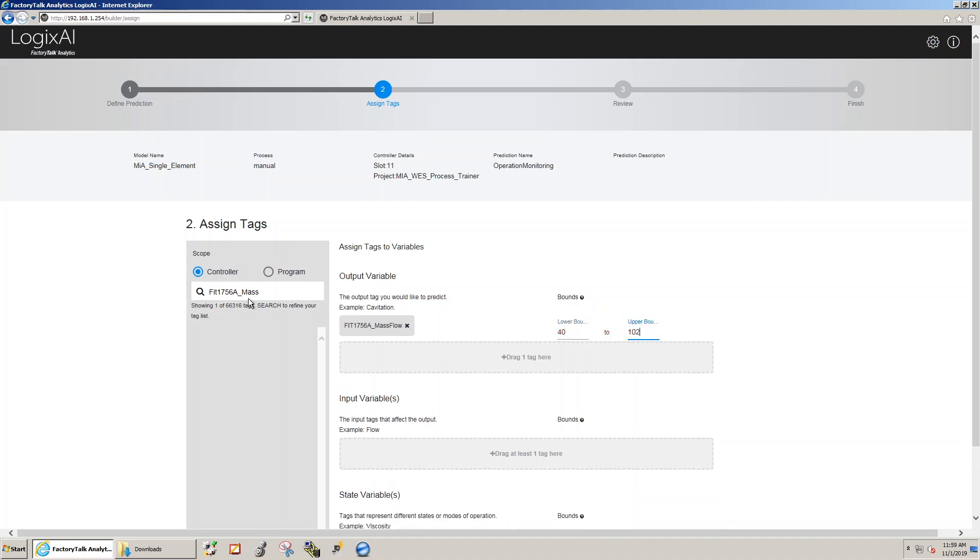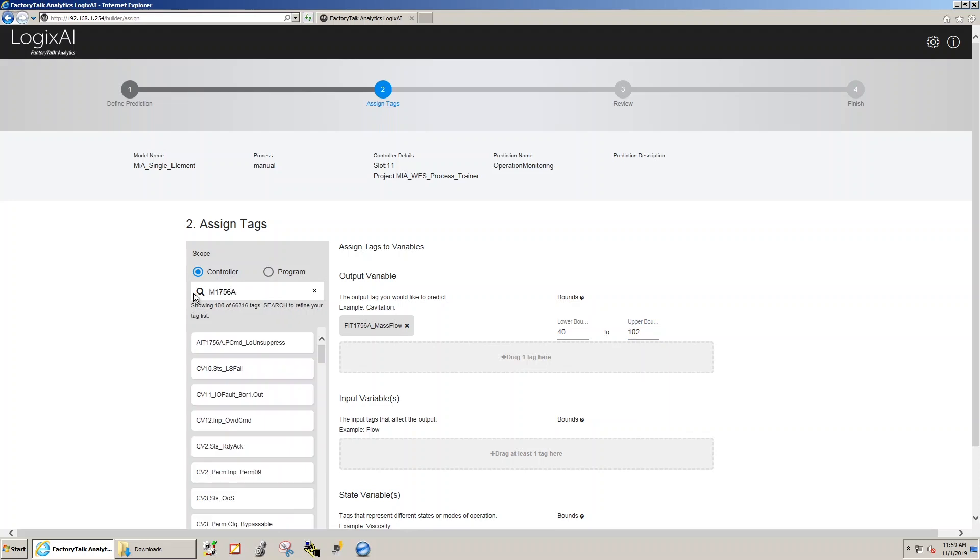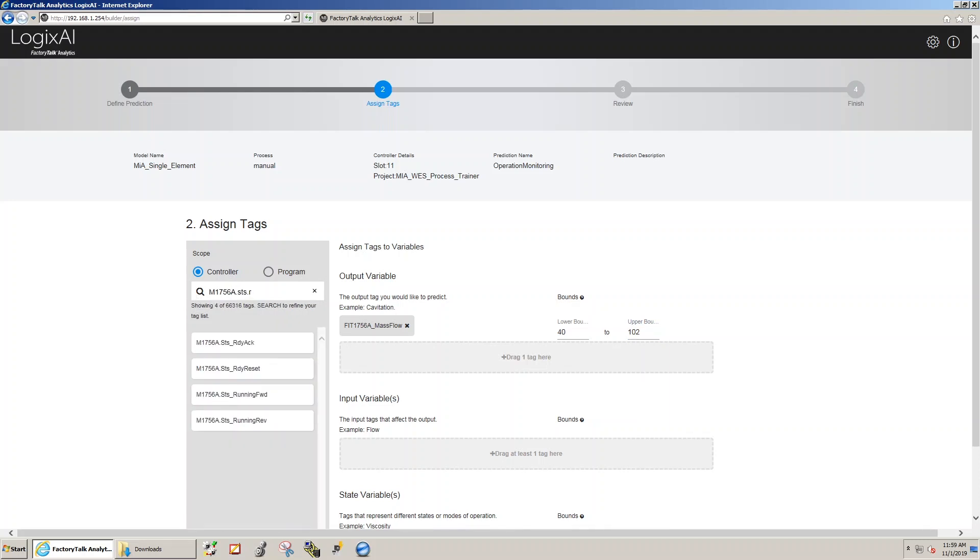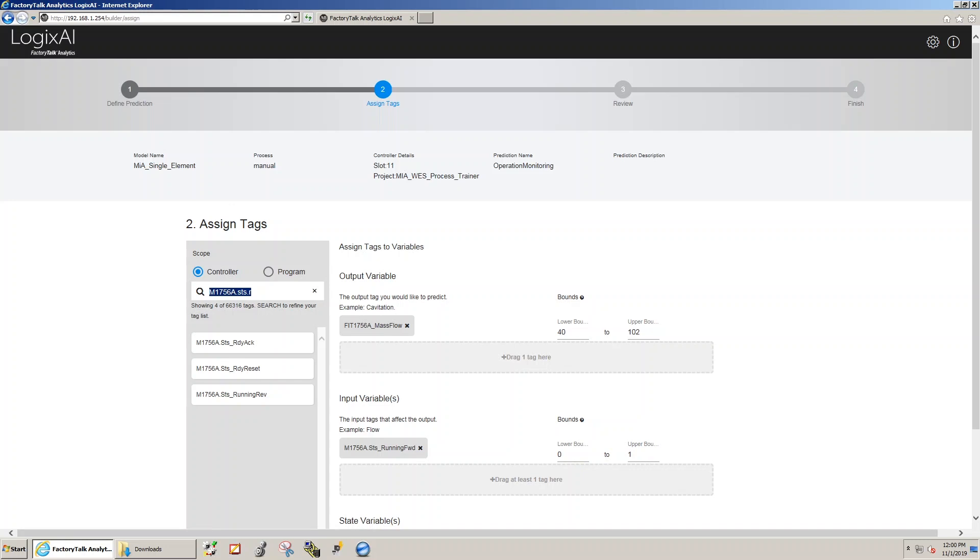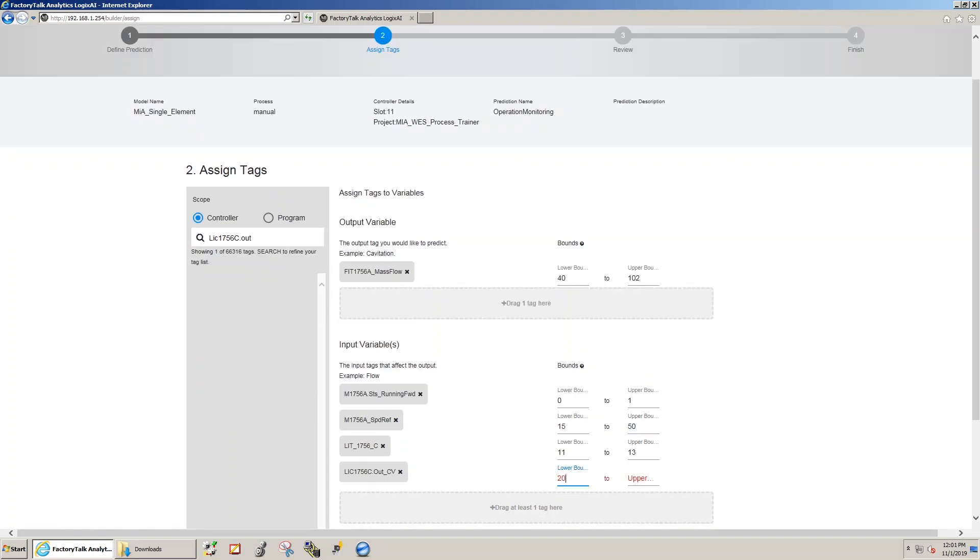As well as defining the tag name, we also have to define ranges which the model will work within on that output variable. In this case, it's 40 to 102 pounds per minute, so we have to keep it within that range while the model is training.